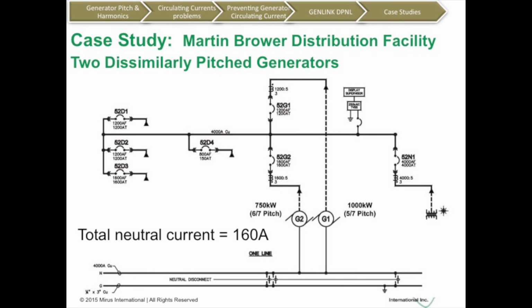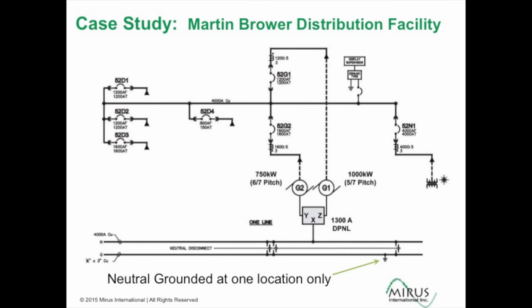So let's look at a few case studies. This first one is a refrigerated storage facility for McDonald's, where generators were being used for backup power. During testing, they noticed that the neutral conductors were extremely hot, and they measured 160 amps in the neutral return, in the neutral circulating between the two generators. So from the selection table, we sized this case to a 1300 amp DPNL, and it was installed in the common neutral of the two generators as shown.